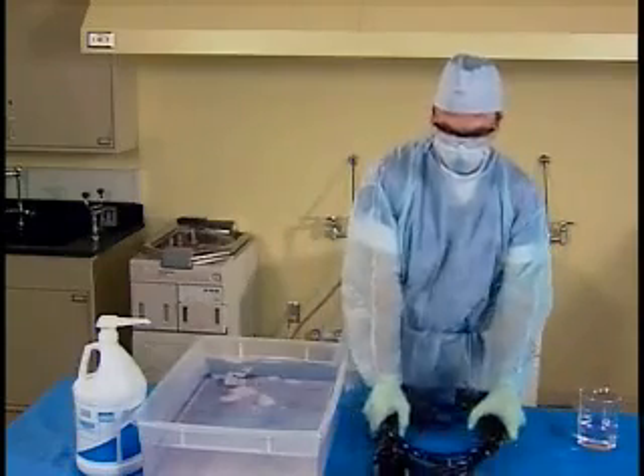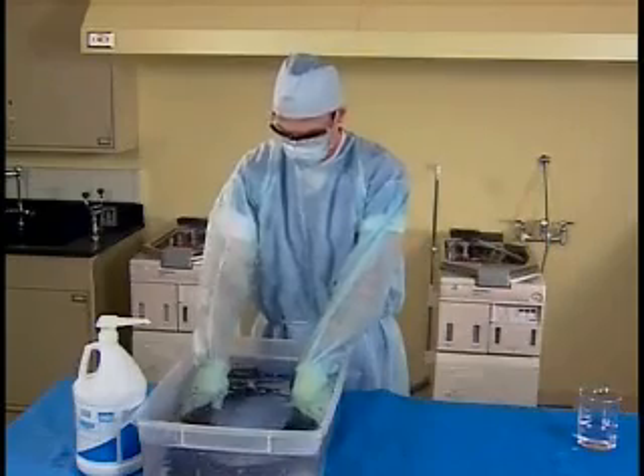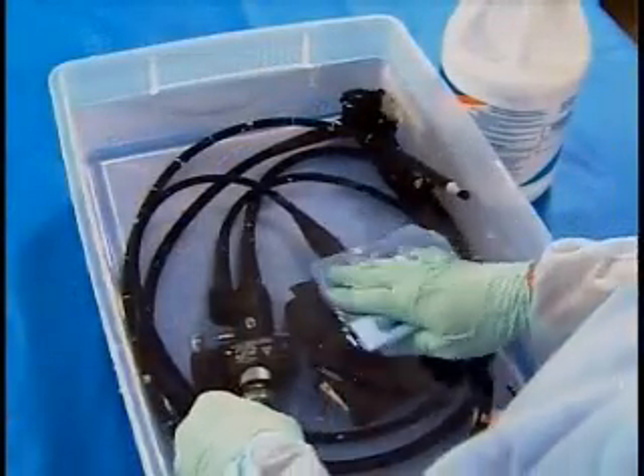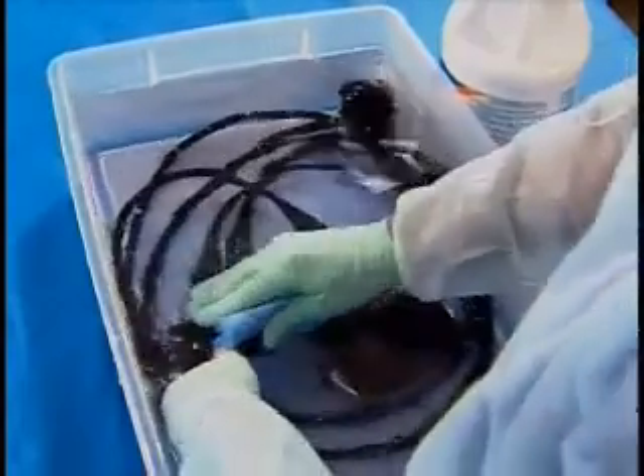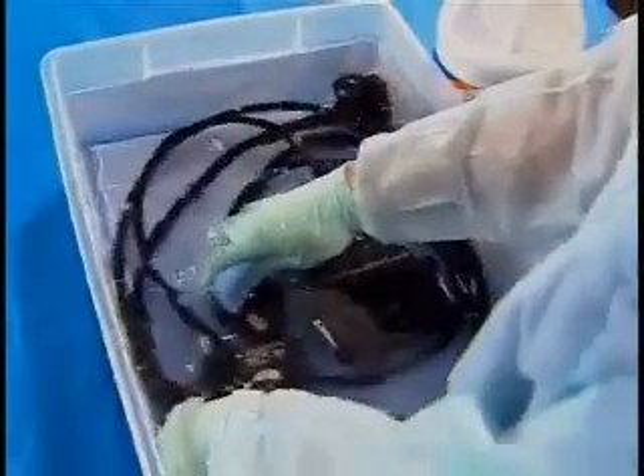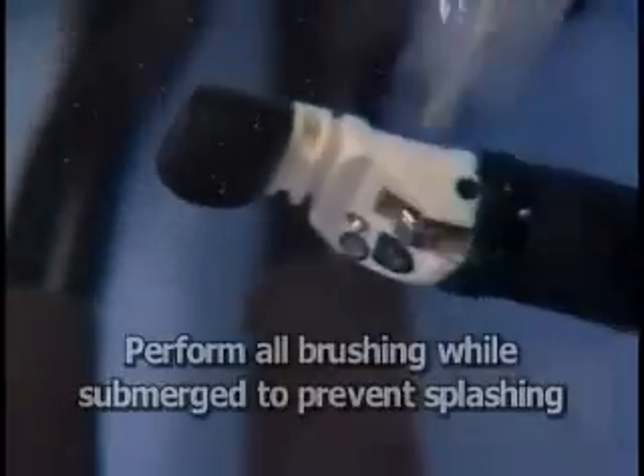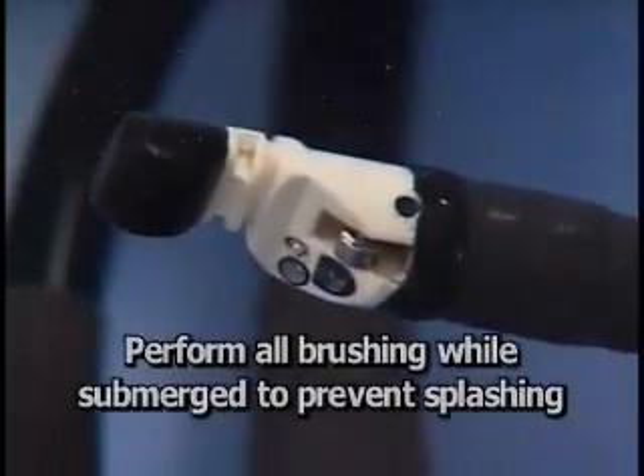Carefully coil the endoscope and completely immerse it in detergent solution. Use a soft brush or lint-free cloth to clean the exterior surface of the endoscope. Pay particular attention to the distal tip and ensure that the air-water nozzle is free of debris. Take care not to scratch the small lenses and transducer. Perform all brushing while submerged to prevent splashing. If you are reprocessing an endoscope with an elevator, raise the elevator and brush the elevator and channel opening.